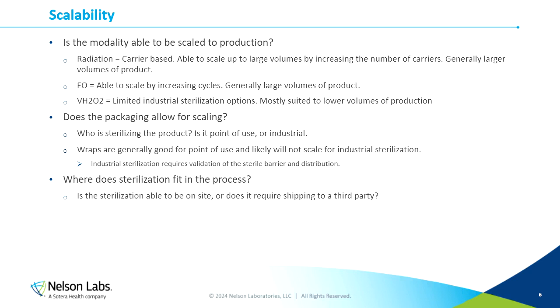So EO, you have the ability to scale by increasing cycles, or also as you validate, including dunnage in your cycles so that you can vary it. But again, it's generally geared towards larger volumes of sterilization. Vaporized hydrogen peroxide is a little bit more limited in the industry at this time. So your sterilization options right now are mostly suited to lower volumes of production, lower amounts of material that is going to be sterilized. So with that in mind, is that something that's going to be able to scale with you being able to make more product, sell more product? Is that something that is going to work for you in the long term?